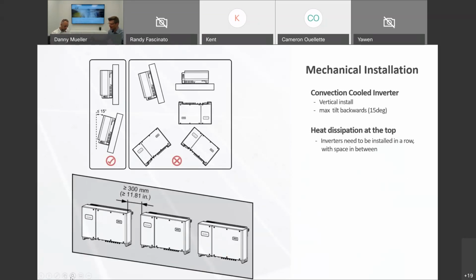When we quickly jump into the mechanical installation, the inverter is a passively cooled system, which means it does not have any fans forcing the air through the heatsink. And with that technology, you have to have convection cooling being built up like a chimney effect through the heatsink of the inverter, which then directly means that the inverter has to be somewhat upright installed on a wall or on a mounting structure. That's why Huawei specifies that the inverter has to be either fully upright, vertical, or can be tilted up to a maximum angle of 15 degrees backwards to maintain that constant airflow at full operation to make sure the inverter is always properly cooled.